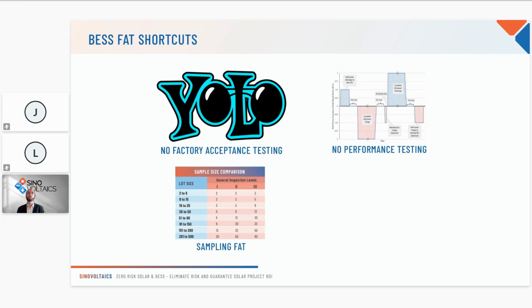Third is a trend we are seeing now in the BESS industry, especially with bigger projects: sampling inspection. So if you buy even 15 or 20 containers, the manufacturer will only allow us to perform FAT on a few samples, maybe 2, 3, or 4 containers. Their thinking is if it's working on those samples, it should work on every container. This is a big shortcut, because today, and for the next few years, the BESS manufacturing process is highly manual. So it's not because 19 containers pass that the 20th container will pass as well. It's another big point to be really careful about in your procurement contracts.